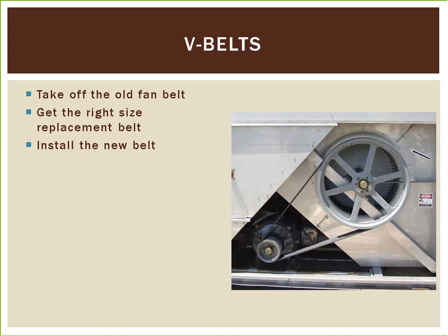Install the new belt. When replacing fan belts, route the new belt so that it uses the exact same path as the old belt. You will need to loosen the hardware securing the motor in order to slip the new belt onto all pulleys. After it is in place, tighten it using the tension adjuster and retighten all hardware.